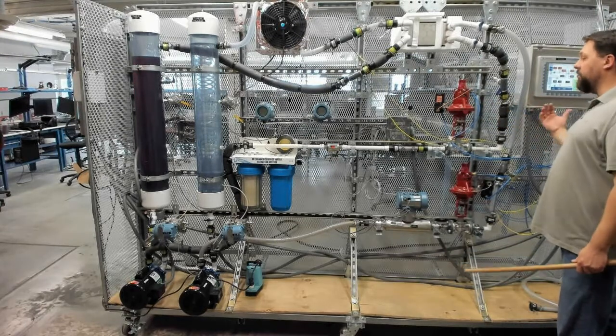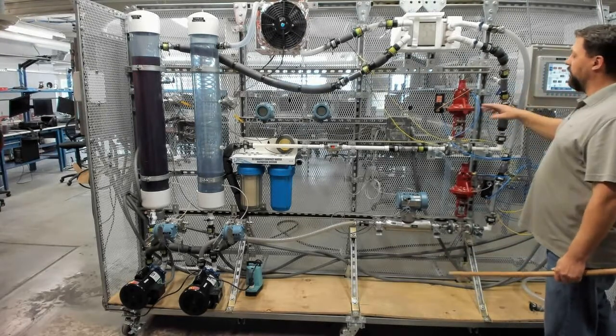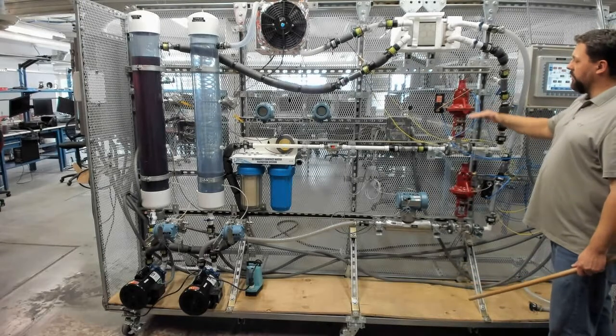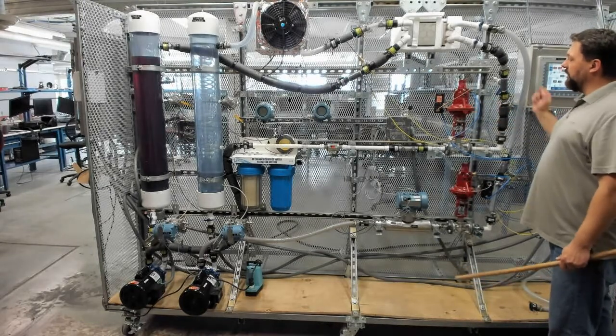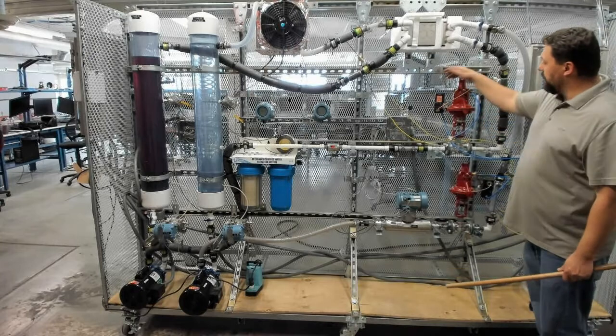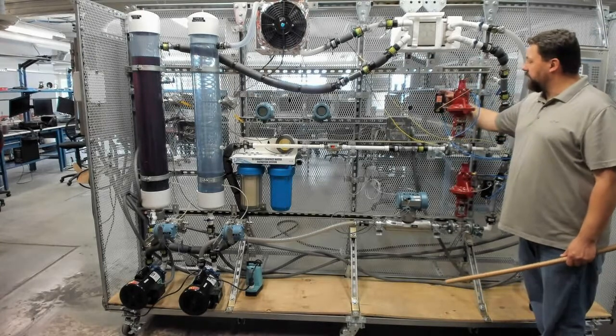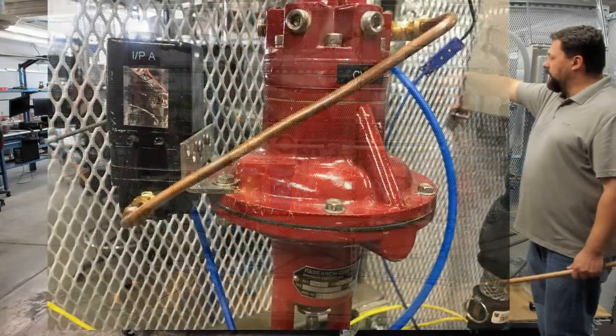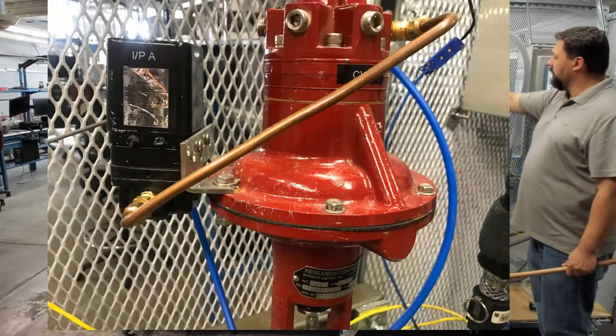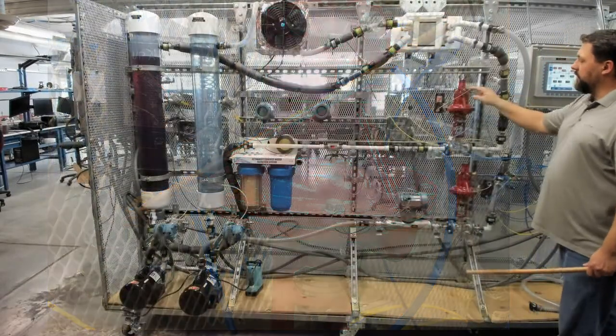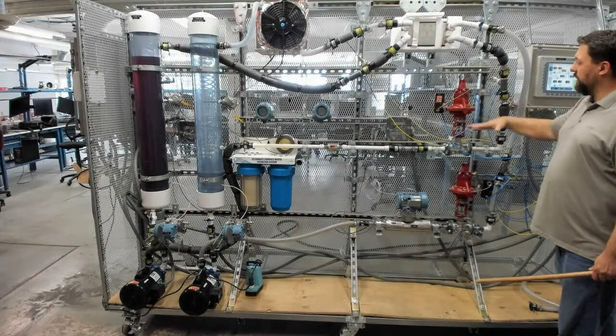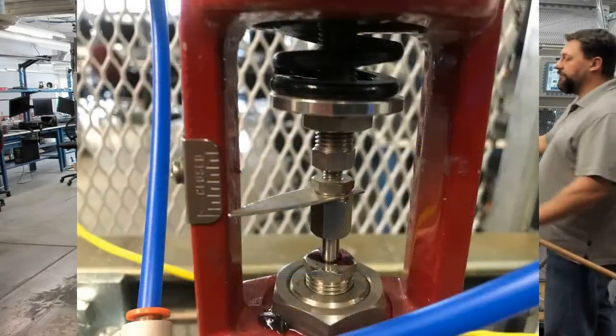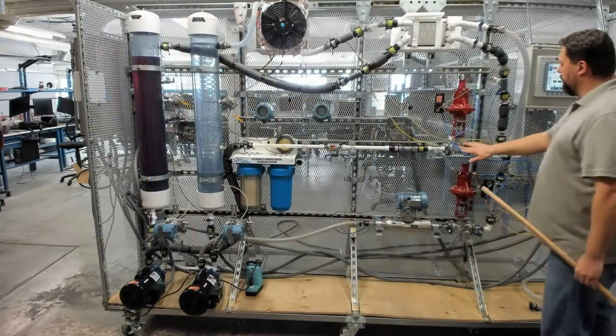If it's in manual mode, we as the operator are going to tell this valve where it should be in position. So we have an electrical signal that comes from the PLC, so that's this wire right here, and this is called an I to P, a current to pressure transducer, and it converts an electrical signal to a pneumatic signal, and it's going to move this valve up and down, thus varying the flow. And so you'll see this move, you'll see this measurement move.